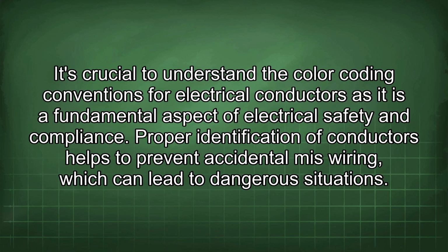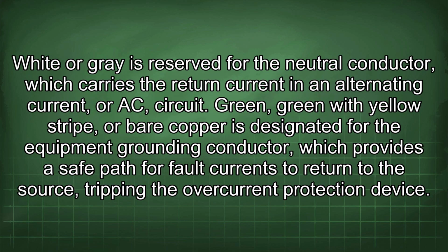It's crucial to understand the color coding conventions for electrical conductors as it is a fundamental aspect of electrical safety and compliance. Proper identification of conductors helps to prevent accidental miswiring, which can lead to dangerous situations. White or grey is reserved for the neutral conductor, which carries the return current in an alternating current, or AC, circuit. Green, green with yellow stripe, or bare copper is designated for the equipment grounding conductor, which provides a safe path for fault currents to return to the source, tripping the overcurrent protection device.